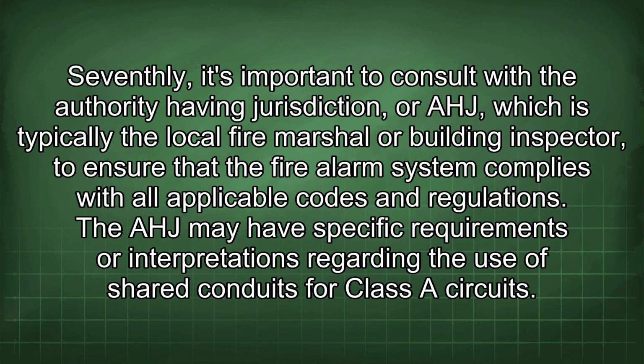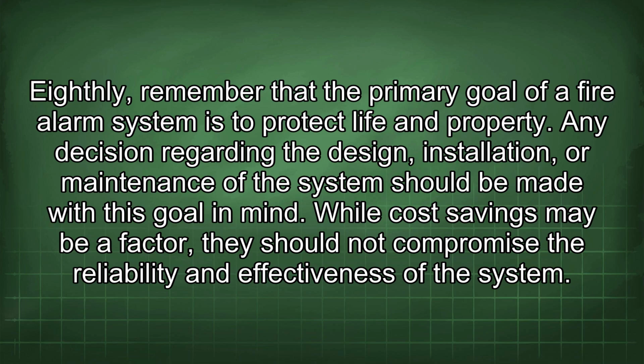Seventhly, it's important to consult with the authority having jurisdiction, or AHJ, which is typically the local fire marshal or building inspector, to ensure that the fire alarm system complies with all applicable codes and regulations. The AHJ may have specific requirements or interpretations regarding the use of shared conduits for Class A circuits. Eighthly, remember that the primary goal of a fire alarm system is to protect life and property. Any decision regarding the design, installation, or maintenance of the system should be made with this goal in mind. While cost savings may be a factor, they should not compromise the reliability and effectiveness of the system.